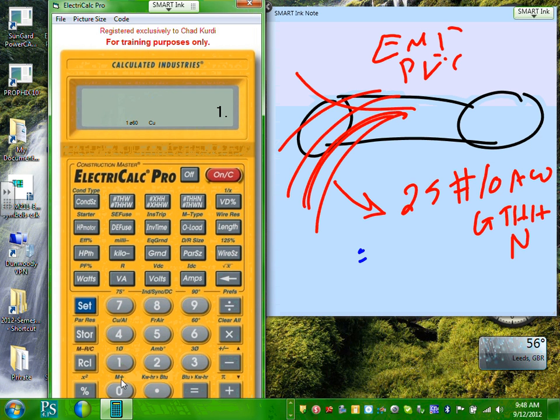So let me just go one more time, guys. Here's my number 10 conductors, and there's 25 of them. Here's 25, and here's my conduit, PVC. If I want to change it into EMT again, I'm going to hit 1, set, conduit. Here's my EMT size. If you want to change it into IMC, it says 4. You hit 4, set, conduit, or you can cycle through them. If you continue hitting it, it will tell you the fill. Look how nice it is. So here's IMC, here's the fill, 32% filling. And here's the area, the square inches occupied in it.